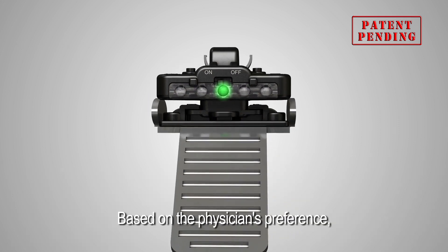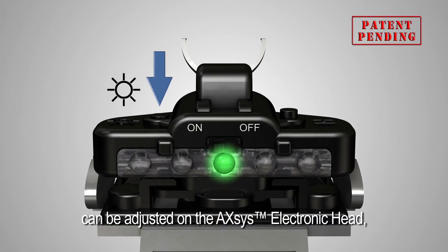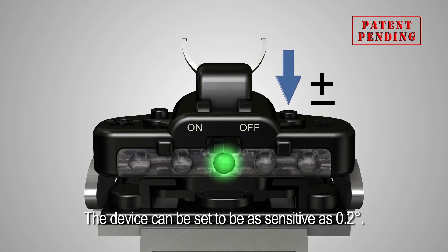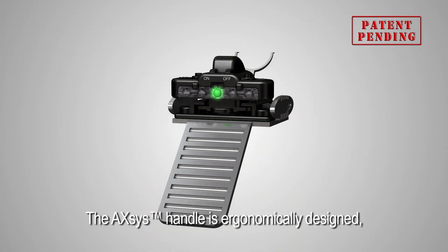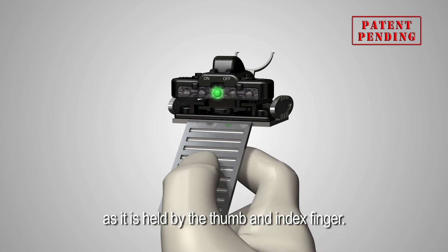Based on the physician's preference, the sensitivity and sound settings can be adjusted on the AXsys electronic head using the buttons on the top. The device can be set to be as sensitive as 0.2 degrees. The AXsys handle is ergonomically designed and offers extreme stability as it is held by the thumb and index finger.